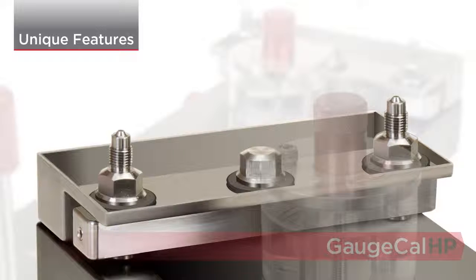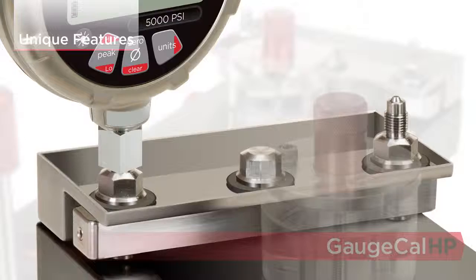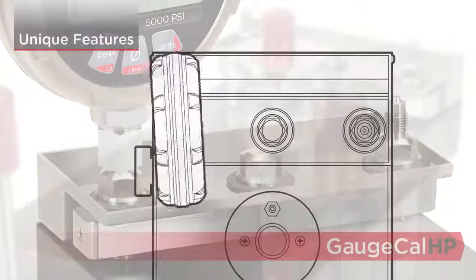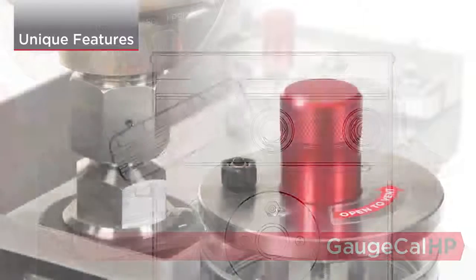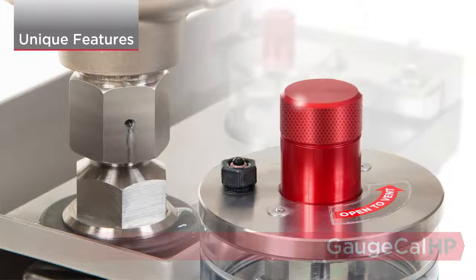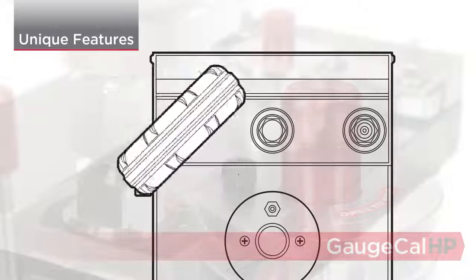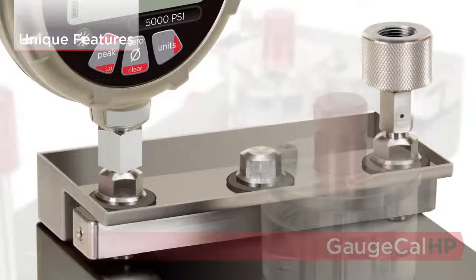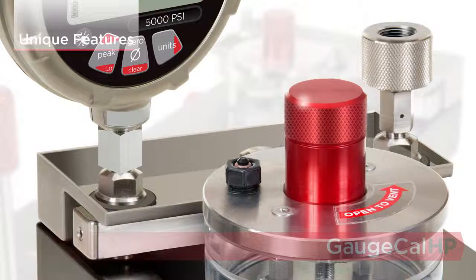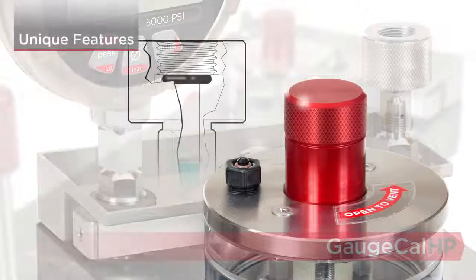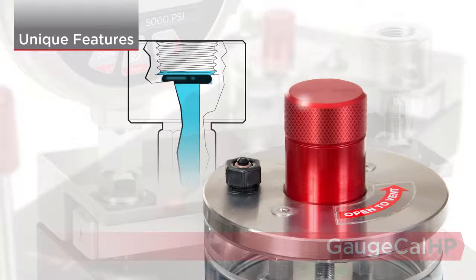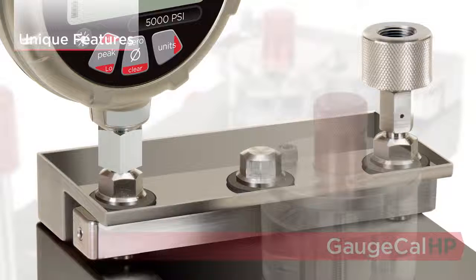The GaugeCalHP has a unique way to bleed trapped air from the system. Start by connecting your Crystal Engineering reference gauge directly to one of the pressure fittings and rotate it about 4 times. Turn the reservoir knob or main handle clockwise until fluid drips from the CPF weep hole. Then tighten the reference gauge. Install a quick test fitting, then turn the reservoir knob or main handle until fluid covers the O-ring. Connect the device under test to the optional CPF quick test fitting.